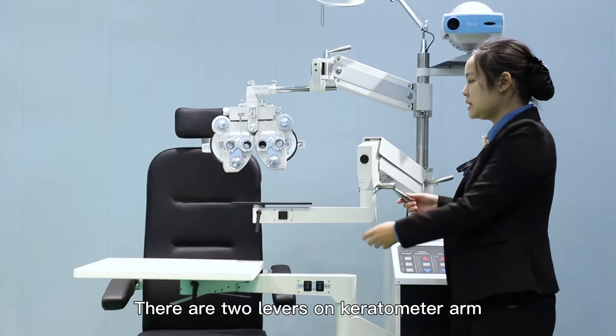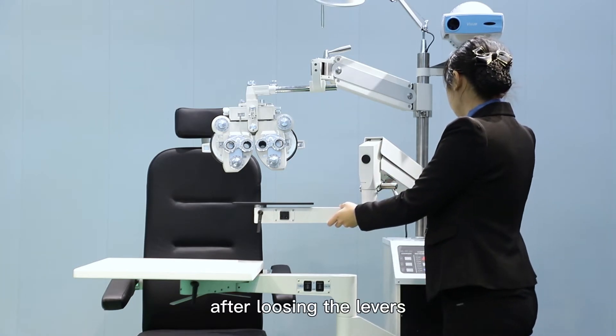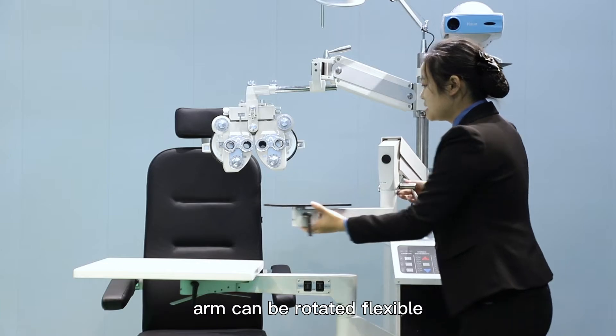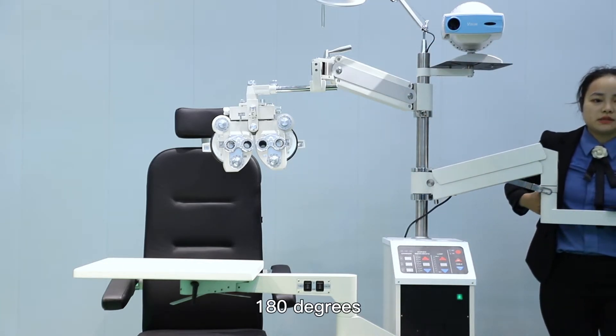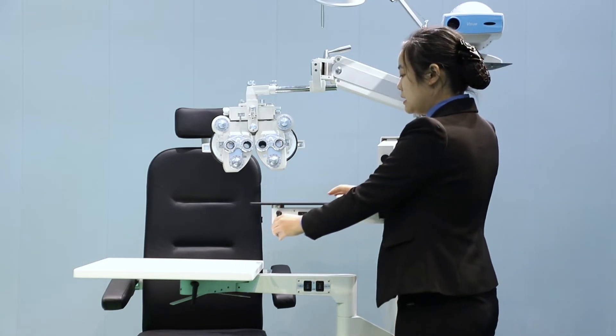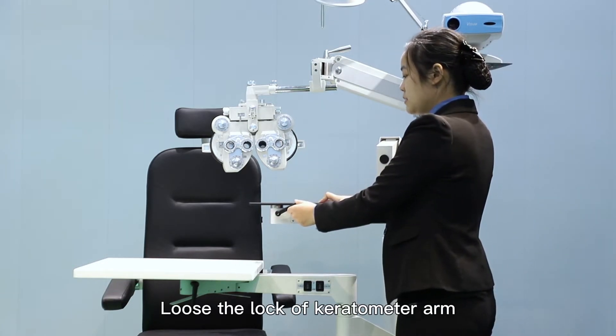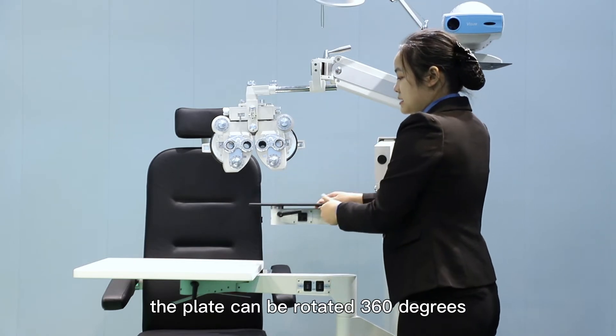There are two levers on the keratometer. After loosening the lever, the arm can be rotated flexibly to 180 degrees. Loosening the lock of the keratometer arm allows the plate to be rotated 360 degrees.